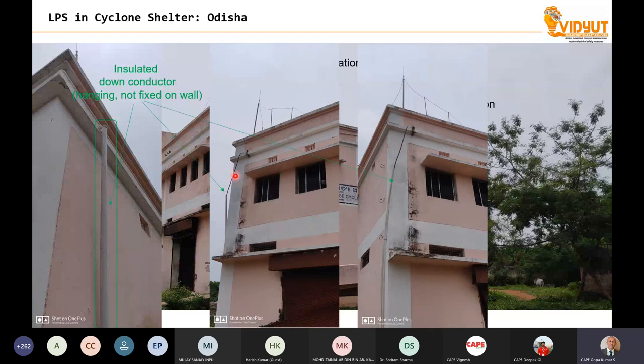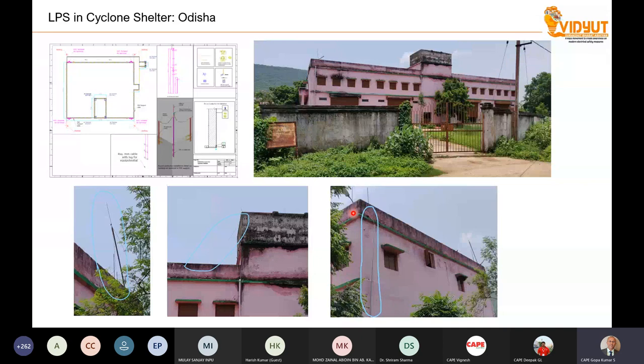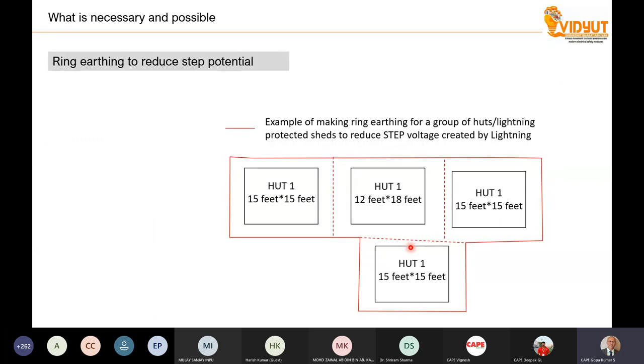Next. The down conductor, very expensive, 3,500 rupees per meter. This conductor is hanging through the pipe, and it is hanging on the side of the building. What kind of installation is it? Number one, this protection itself is not required. You have provided a protection. Of course, probably the people are protected. But how are these installed? I'm not showing the installation of a 10 years old picture. This is very recent. It is installed, I think, only 2 years back. The entire thing is destroyed within 2 years. So these are the facts about the lightning protection stories going on in India.